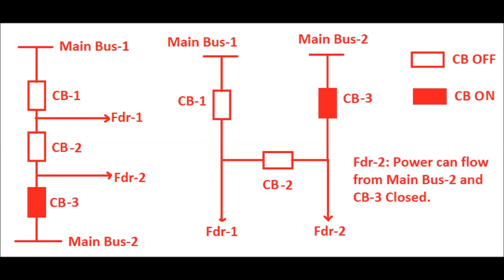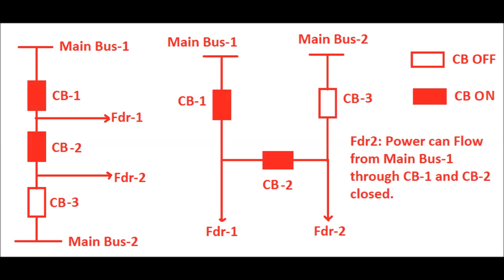Similarly, how does feeder 2 get power? There are two options: one from main bus 2 and another from main bus 1. From main bus 2, feeder 2 can receive power through CB3 in closed position — CB3 being the circuit breaker towards the main bus 2 side. Again, feeder 2 can also receive power through main bus 1, in which case CB1 and CB2 must both be in closed positions. Isolator positions are not shown here for ease of understanding.